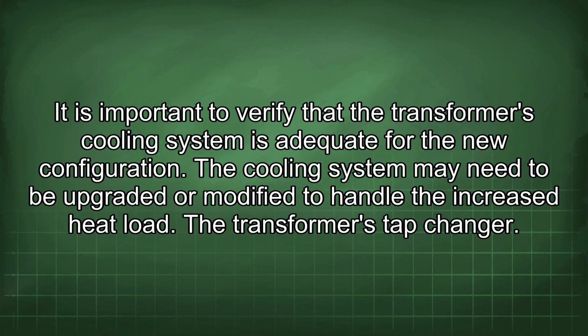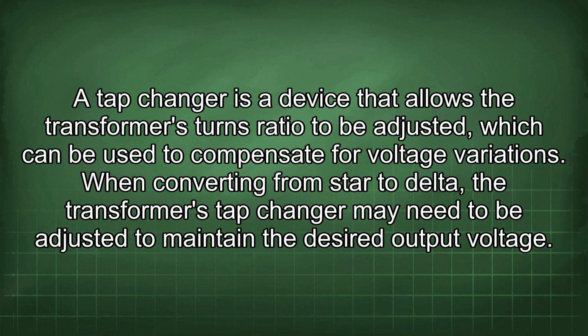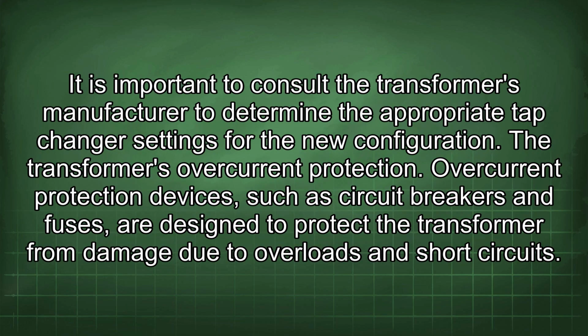The transformer's tap changer. A tap changer is a device that allows the transformer's turns ratio to be adjusted, which can be used to compensate for voltage variations. When converting from star to delta, the transformer's tap changer may need to be adjusted to maintain the desired output voltage. It is important to consult the transformer's manufacturer to determine the appropriate tap changer settings for the new configuration.